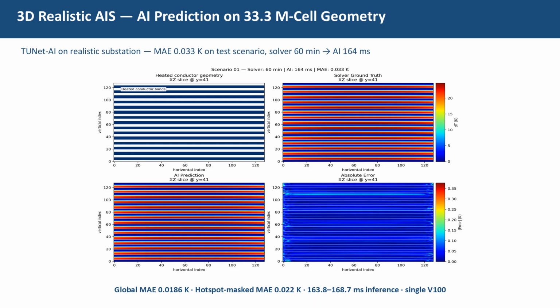Here is the critical result. The TUNet champion, trained on the scaled campaign and fine-tuned on realistic AIS subvolumes, applied to a 128-cube test subvolume of the full 33 million cell substation geometry. The 4 panels show, from top left, the conductor band geometry, the solver ground truth, the AI prediction, and the absolute error field. For this scenario, mean absolute error is 0.033 Kelvin. Wall clock time, the solver takes 60 minutes, the AI, 164 milliseconds.